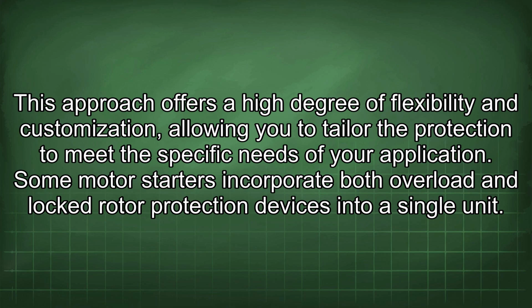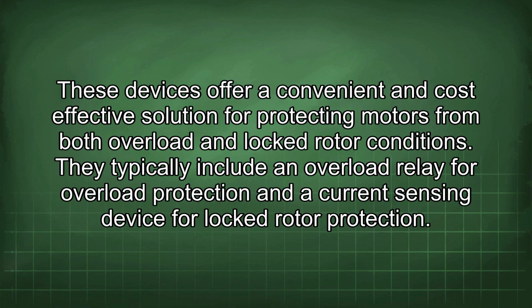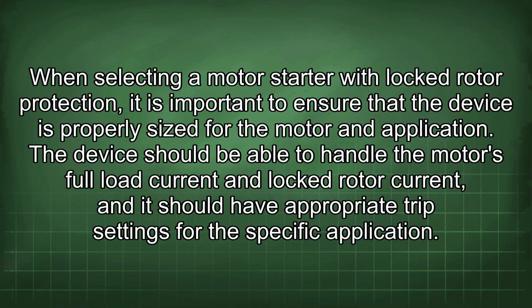Some motor starters incorporate both overload and locked rotor protection devices into a single unit. These devices offer a convenient and cost-effective solution for protecting motors from both overload and locked rotor conditions. They typically include an overload relay for overload protection and a current sensing device for locked rotor protection. When selecting a motor starter with locked rotor protection, it is important to ensure that the device is properly sized for the motor and application.